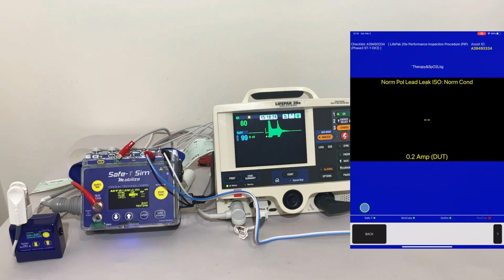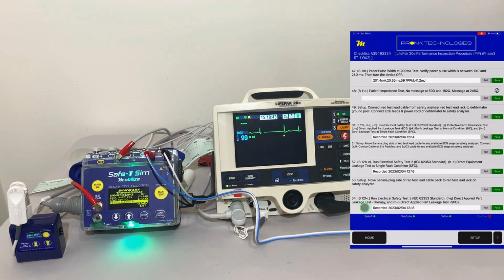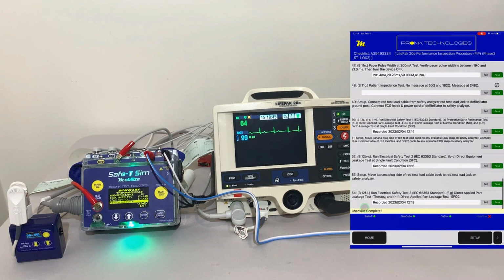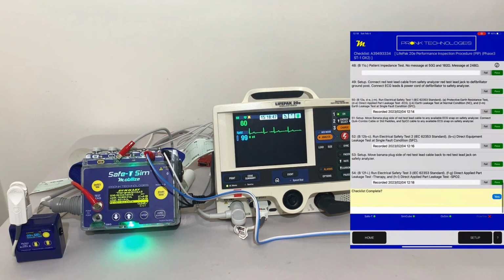So again, the procedure knows exactly what tests need to perform. You as a technician will just press the run button and it will automatically perform those tests and verify that the results are within the specified limits from the service manual for the LifePak. We've completed all of these tests, and now we're done. We've completed the entire procedure involved based on the manufacturer's requirements for testing the LifePak 20E, and we can go ahead and say we've completed this procedure.